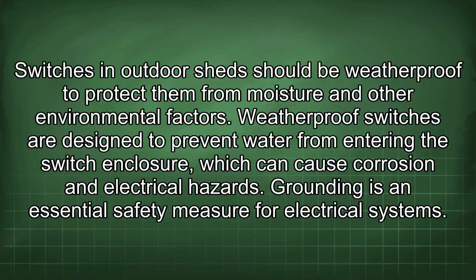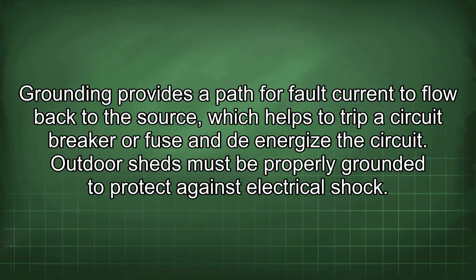Switches in outdoor sheds should be weatherproof to protect them from moisture and other environmental factors. Weatherproof switches are designed to prevent water from entering the switch enclosure, which can cause corrosion and electrical hazards. Grounding is an essential safety measure for electrical systems. Grounding provides a path for fault current to flow back to the source, which helps to trip a circuit breaker or fuse and to de-energize the circuit.